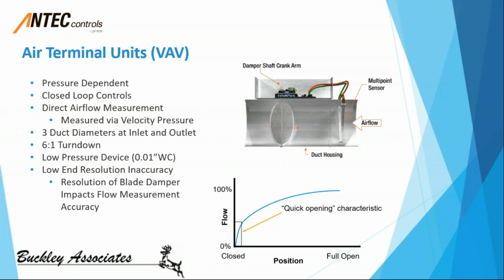So once again, looking back at a standard VAV box, closed loop controls and a pressure dependent system, airflow is measured and a signal is sent to a controller that moves the blade damper that adjusts the airflow. This closed loop can often lead to slower response times as the system has to balance itself out. Also, these units require some sort of straight ductwork leading into the unit and exiting the unit to encourage laminar airflow. The reason for this is to ensure that the airflow velocity measurement being taken is accurate. Without laminar flow through this device, we're going to have an inaccurate measurement and the device is not going to be able to function as designed.